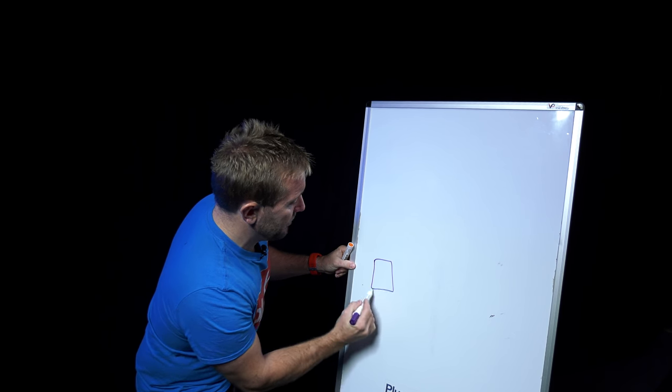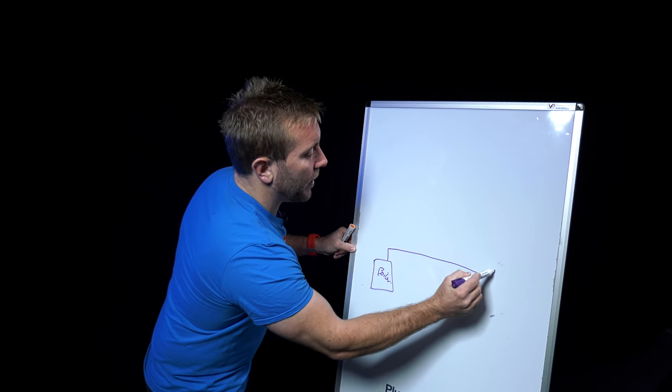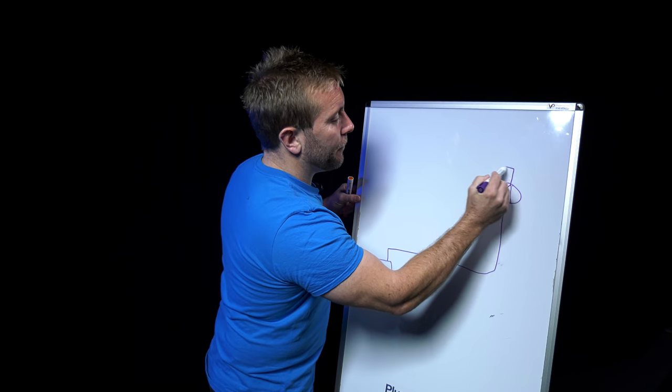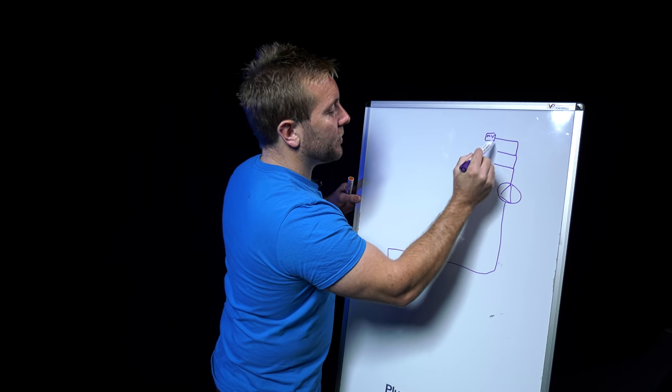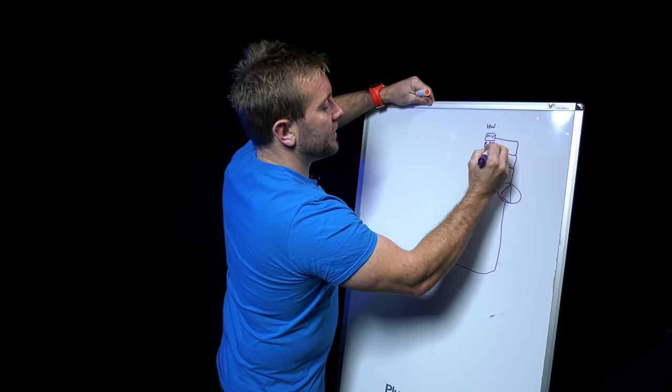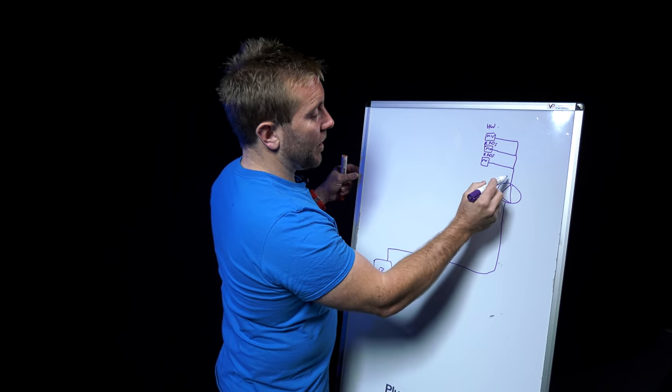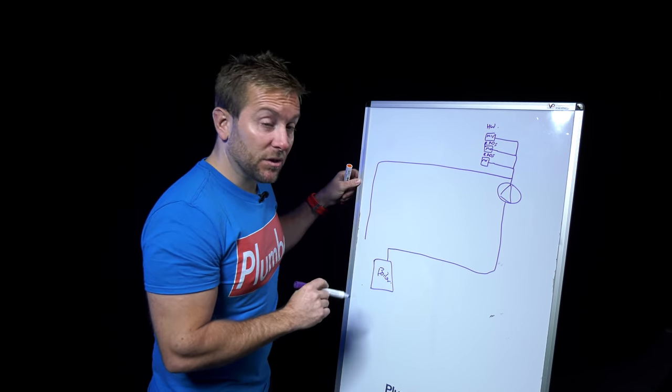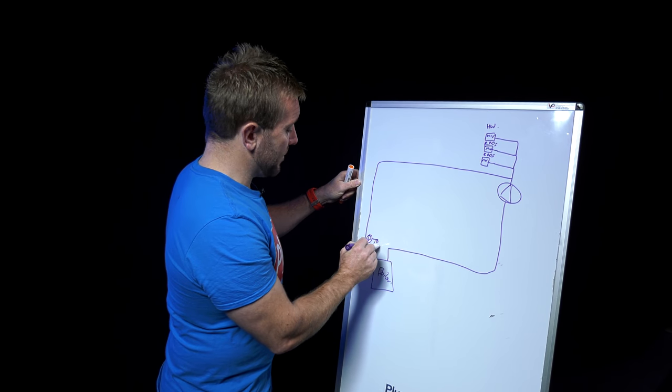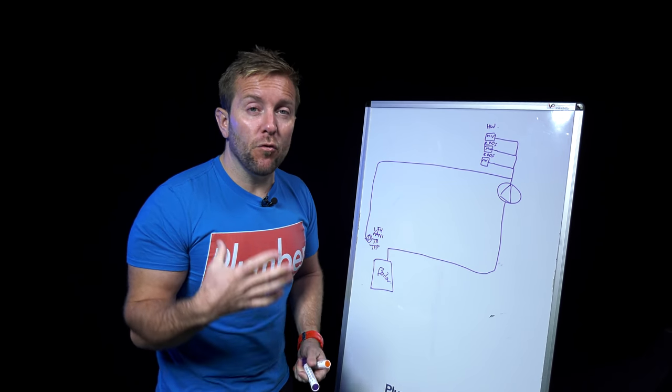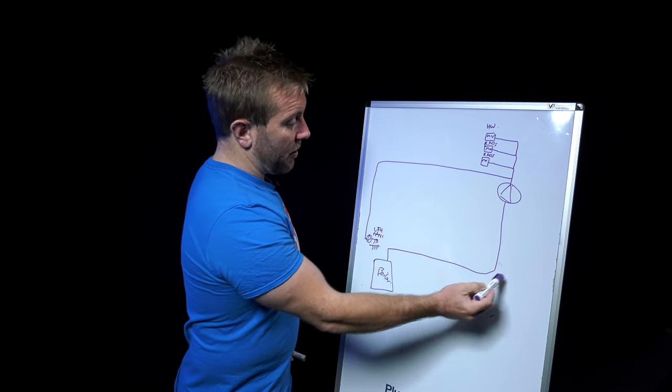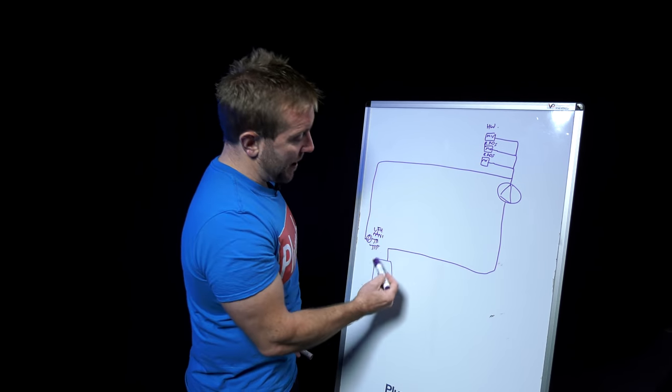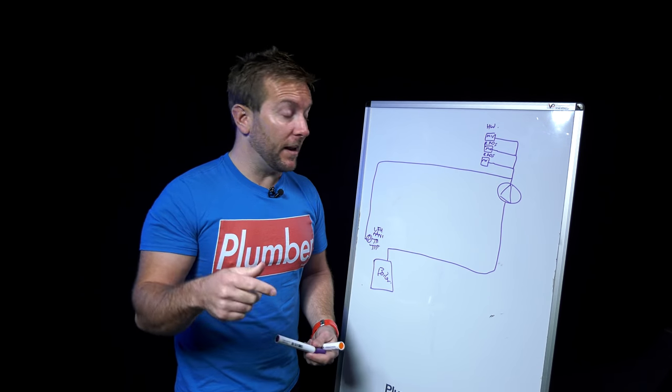So what do relays do? Relays interrupt the live supply to a component in the system that you do not want to come on, but you can still control whether it's interrupted or not using time clocks and thermostats. So how did I use relays to solve the problem of fixing that heating system? Well let's have a little look. So this is what we had. We had a boiler and the flow from that boiler went all the way, miles away, into an airing cupboard to a pump, and from there we had motorised valves for hot water and upstairs and downstairs rads. Coming off the back of that, up in the airing cupboard, we had a pipe that came all the way back to a room just next door to the boiler that went to a small pump and an underfloor heating manifold.